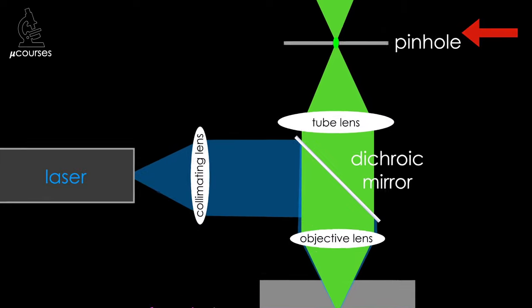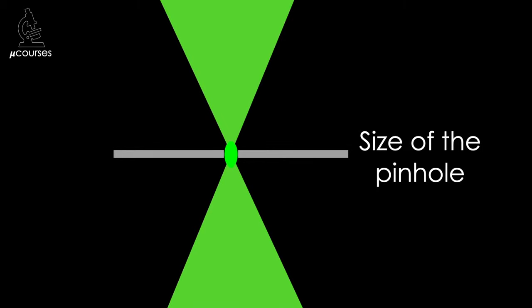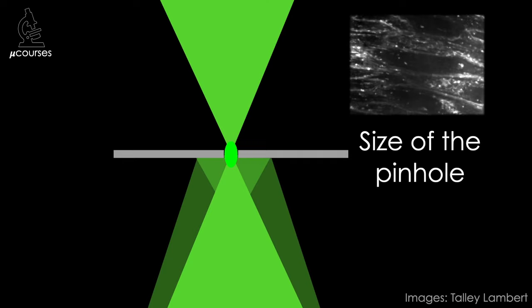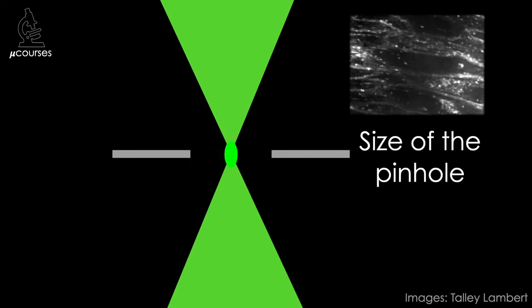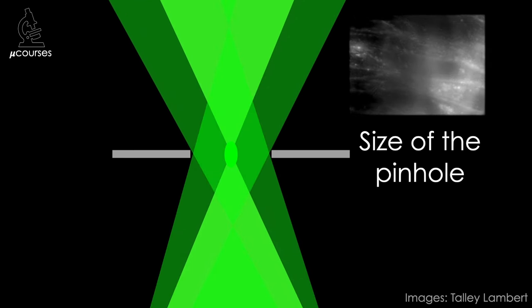Now let's look more closely at the pinhole, specifically how the size of the pinhole affects image quality. When the size of the pinhole matches the size of the image focused on the image plane, the maximum amount of out-of-focus fluorescence is blocked. As the diameter of the pinhole increases, more out-of-focus light is able to pass through, so the size of the pinhole is an important parameter in confocal microscope performance.